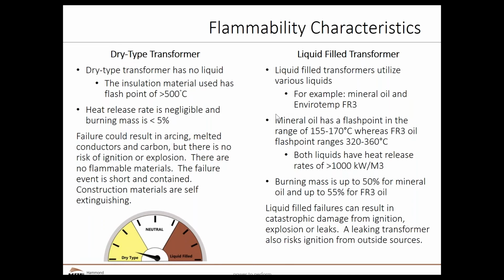Flammability characteristics are important. With dry type transformers, there is very little, if any, ability to burn anything. About the only thing that might be able to really combust within a dry type transformer might be the varnish, depending on what type of varnish we're using. And that would be less than 5% of the total mass of the transformer. And that tends to be self-extinguishing even then. So there is very little concern of flammability with a dry type transformer. If it does fail, you'll probably have some release of smoke, but we're not worried about burning down a building or starting other fires.